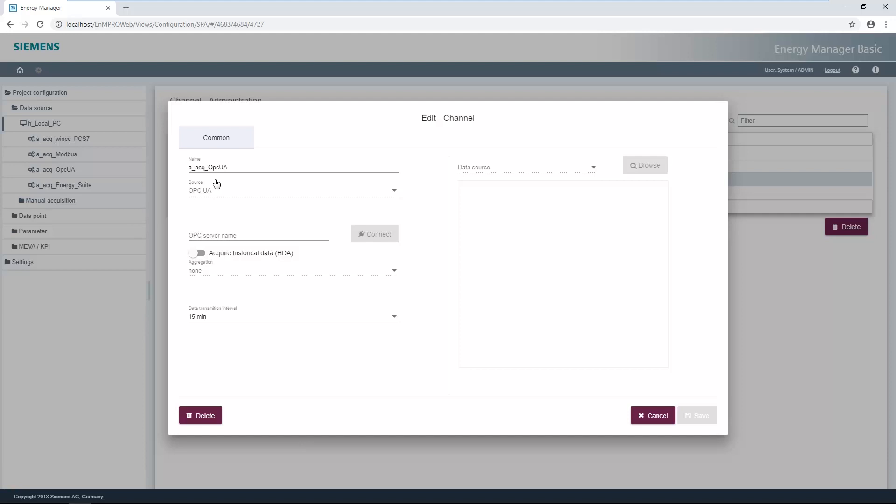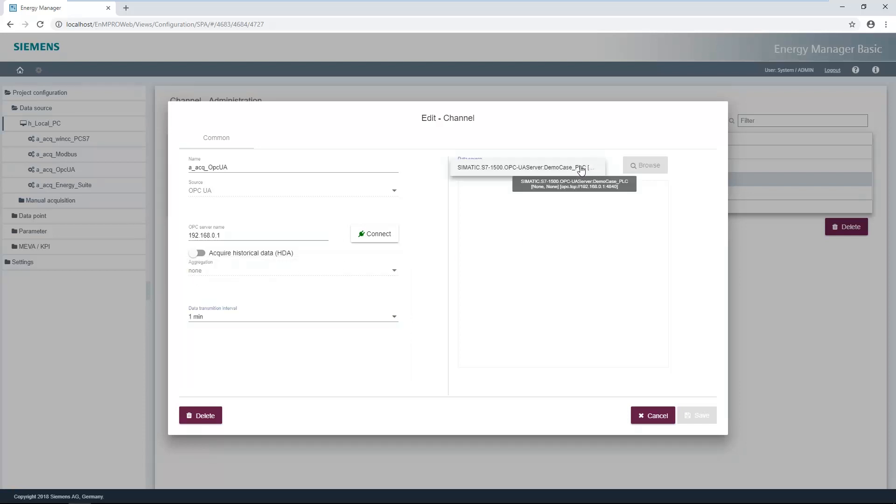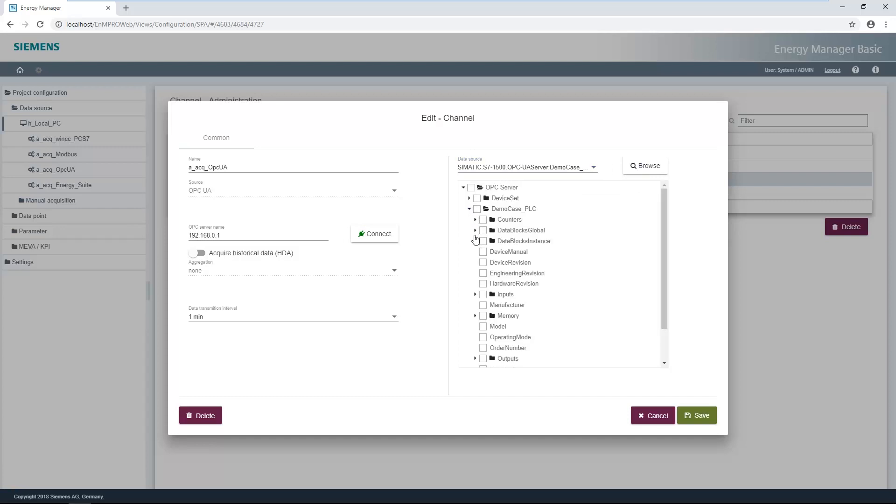The OPC UA server of the 1500 CPU is used to record the production quantity. The IP address of the CPU's OPC UA server is first required for the OPC UA channel. The connect button establishes the connection to the device with the OPC UA server. Then the cycle time of the data point has to be set, and the OPC UA server must be selected.